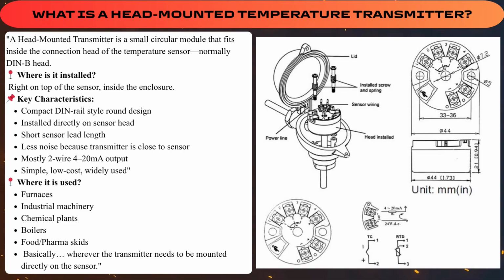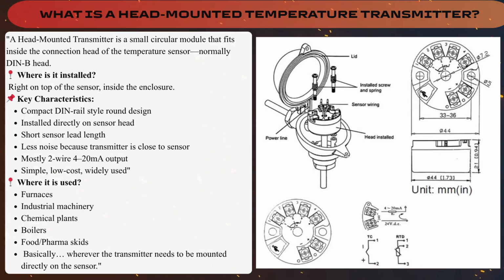Short sensor lead length. Less noise because transmitter is close to sensor. Mostly two-wire 4 to 20 milliampere output. Simple, low cost, widely used. Where is it used? Furnaces, industrial machinery, chemical plants, boilers, food pharma skids. Basically, wherever the transmitter needs to be mounted directly on the sensor.